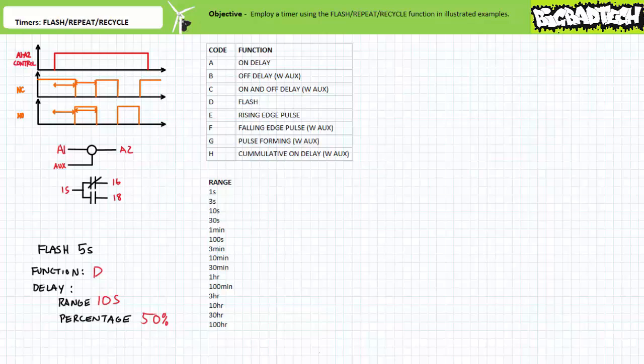Troubleshooters take note: a multi-function timer executing the right function at the wrong time needs to have the delay adjusted. In contrast, a multi-function timer executing the wrong function at the right time needs to have the function adjusted. Misinterpretation of functions is not as rare as one might think. Also note that timers executing the on-delay or off-delay sometimes have unique schematic symbols, but timers executing the flash function are often represented schematically as regular normally closed or normally open contacts. The documentation associated with the ladder logic diagram should clearly indicate these contacts are performing the flash function.